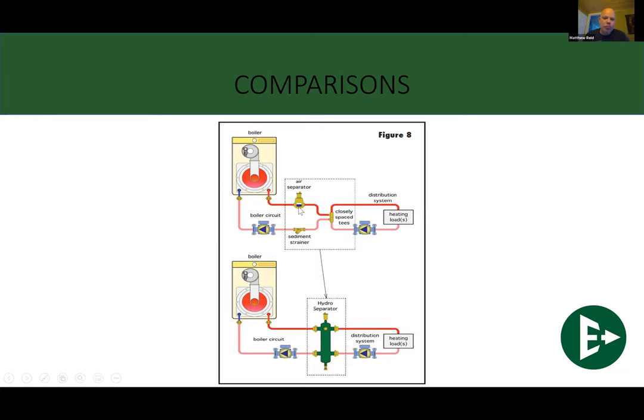So we have, in theory, two potential leak points in the air separator, four potential leak points in the closely spaced tees, and another two in the sediment strainer, for a total of eight potential leak points. Not only that, but it's also three different pieces of equipment. Whereas a low-loss header slash hydro separator has all those things built into one. The air separator is built in, the closely spaced tees are built in, the dirt separator is built in. So when we're talking about putting a system underneath a set of stairs, this has got everything that you want built into one. Save that space by putting in one piece. And you can take care of all the issues of wondering, is it the boiler, is it the system? This will tell you. If the boiler's working fine, it'll be sitting there working just fine. So you'll be able to see it in real time.